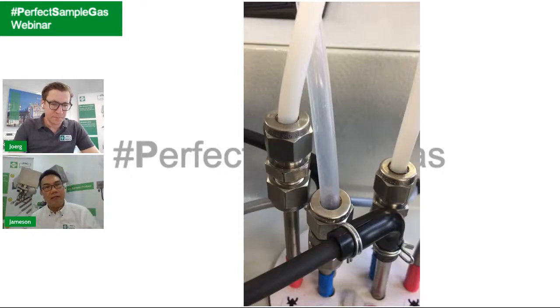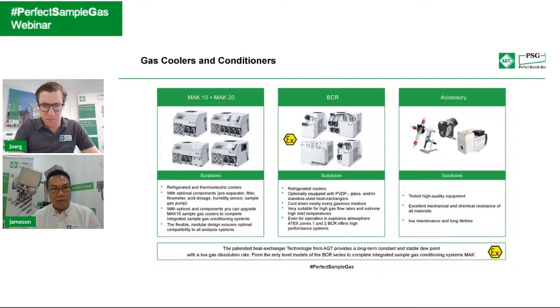It dissipated all the heat, which means the sample at the point of entry is now below the acid dew point, below the water dew point. The purpose of the cooler, and why it is so expensive, is to do a thermodynamic exchange, whereby the very hot gas comes in, and the cooler has to take this impact in the shortest time and cool the very hot sample all the way down to 3 degrees C. That moment of thermodynamic squeeze takes out all the water. But many system integrators have made this big mistake, whereby the naked or unheated tubing, as long as 1 meter, defeats the purpose. That is one reason.